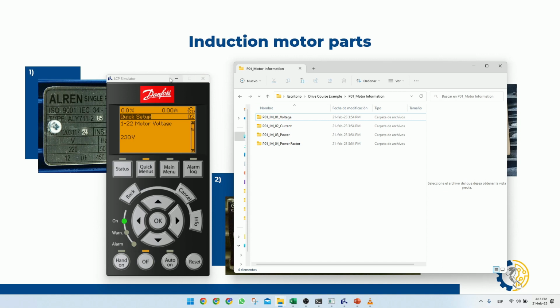So here, the only option that it's asking us for is torque characteristics or application that we're going to be handling. This is incredible because the control type is already being calculated directly by knowing what type of application it is about. Is it a constant speed? Is it something that is changing for a certain time?